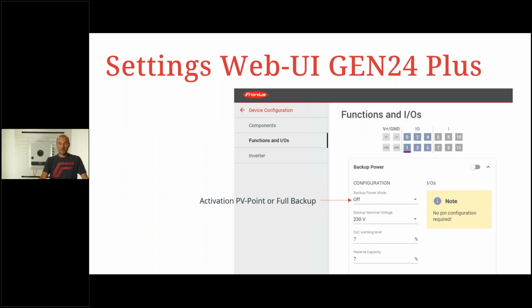For the settings on the web UI, when you do the commissioning the first time, you will come to this point, functions and IOs, and here you just need to get to the point backup power, activate backup power, and then backup power mode PV point or full backup. Full backup means full for the whole household with this automatic switchover or manual switch, and PV point comfort or PV point standard. So you can select this here, you save the settings, and that's it basically. So not more to do.